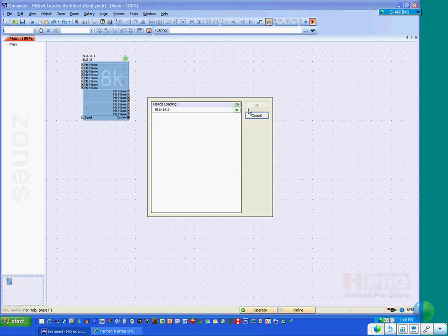When I hit the load button, what's going to happen is this design file is going to be loaded into my Blue 16. Every device has as its device password, its box password, whatever the box password was of the last design file loaded to it. The most recently loaded design file's box security password. So in this case, when I hit the button, I'm now setting my box security password on that Blue 16 to dog, which is my password to this design file.